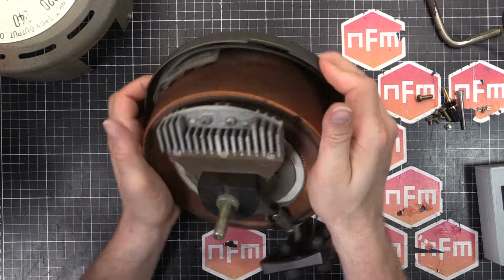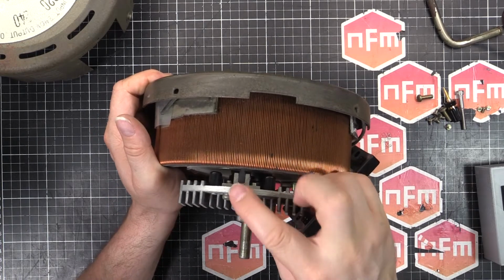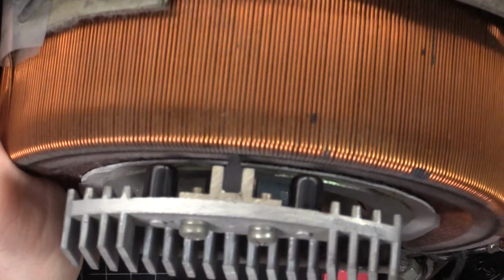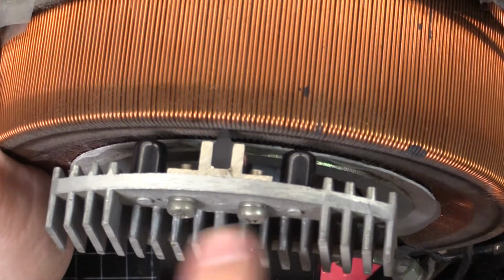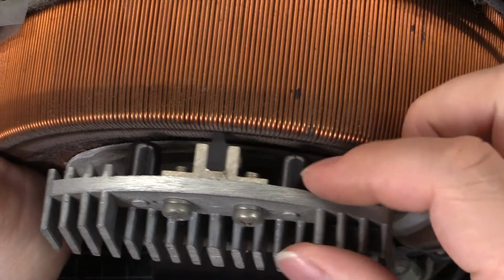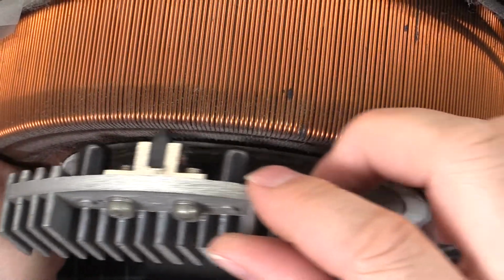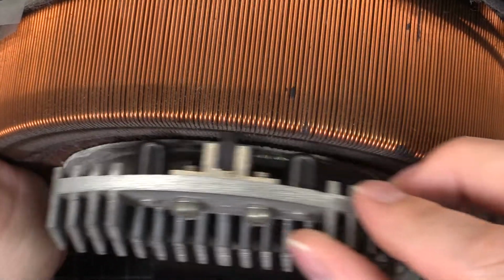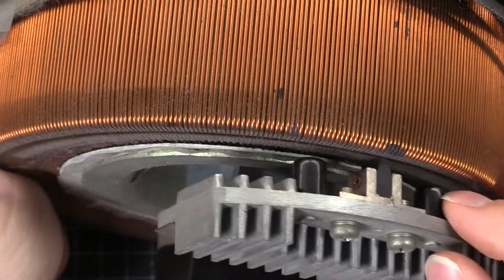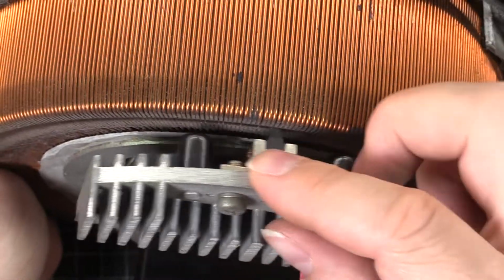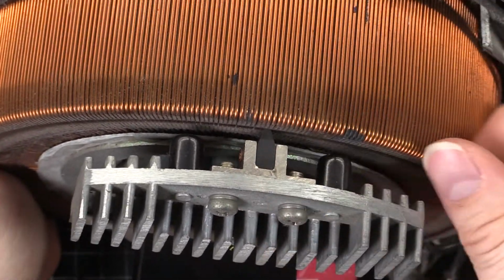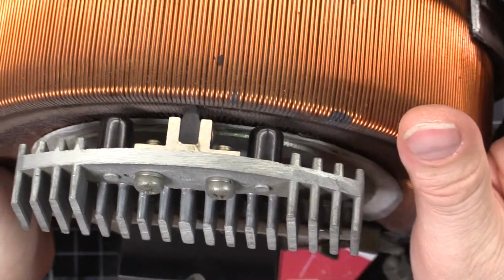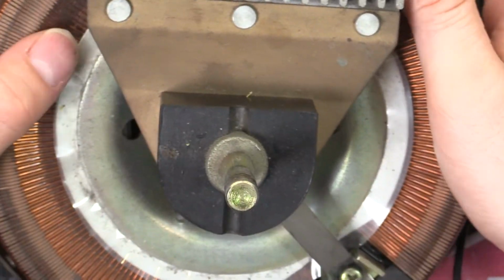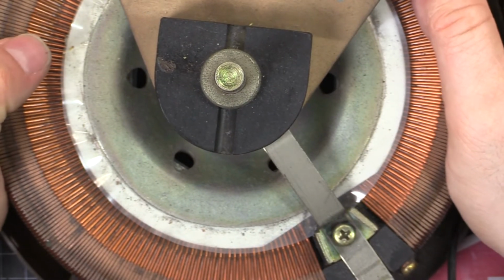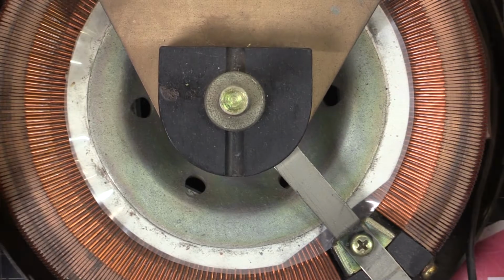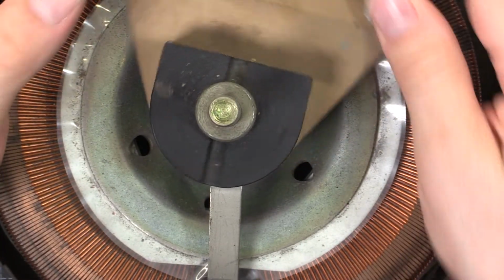So if I tip this up, oh man, you can see there's our brush. I'll zoom in a little bit. So that's just a little thing there, 2 screws, and then this whole section comes out with the carbon in there. That's what rides along and gives us our contact - nice and smooth with the graphite there, and it's about, I guess, 10 mil deep. So it's got a good amount of width there to pass a good amount of current. This will output maximum 10 amps, or 2 kilovolt amps - 2 kVA at maximum of 10 amps. So it's a good size for testing things on the bench.